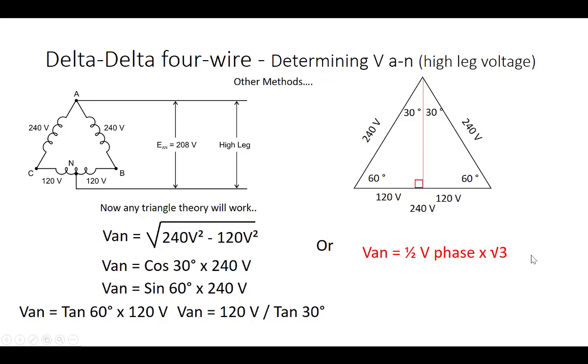We just simply say that the A to N, the high leg voltage, will be half of my phase voltage. So if my phase voltage is 240 volts, it will be half of that, or 120 volts times root 3. And 120 volts times root 3 will give me a high leg voltage from A to the center tap or neutral point of 207.8 volts. To memorize a little formula like this is, I think, an easier way to do it than to try and figure out the vector math for it.